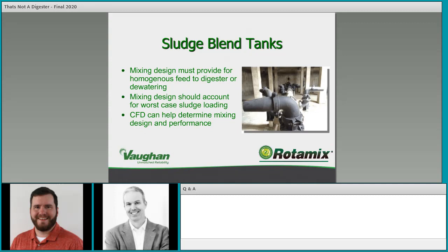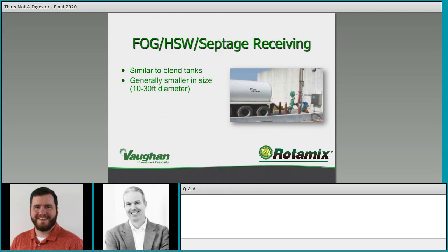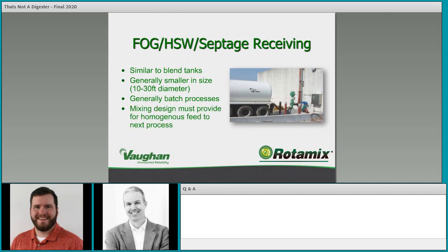FOG — fats, oils, grease — high-strength waste, and septage receiving are similar to blend tanks but with some key differences. They're generally smaller in size, 10 to 30 feet in diameter, and tend to be standalone systems. They're generally batch processes: you're offloading a truck, mixing and homogenizing, maybe taking lab measurements to check pH or other parameters, and then once cleared, sending it on to your process — perhaps a blend tank or directly to a digester.